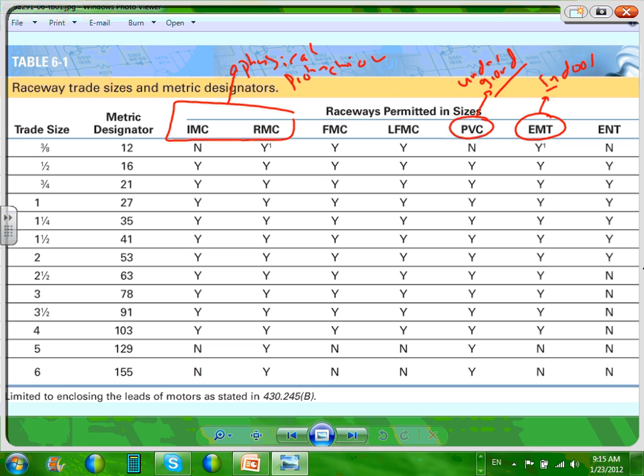Hazardous location, rigid. So you wouldn't touch rigid unless you have a reason for it. I always say rigid is 10% of what you will use, if even 10%. I would say EMT, you're going to have at least 90% of your conduit will be probably EMT. PVC underground, probably 20% if I will throw. They don't have to add up to 100, by the way. 20% of the time they're going to be using it.